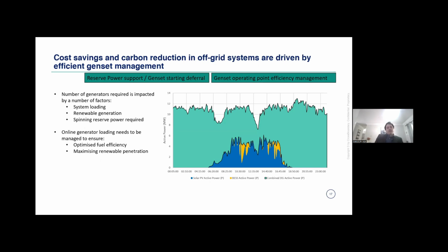Another critical application that we applied was on the reserve power support and genset operating point efficiency management. So when we look at a microgrid, obviously the number of generators that's required is impacted by the system loading, the renewable generation at the specific time, as well as the spinning reserve power required, which is a very critical aspect and which also reduces efficiency because you end up running more gensets than required for the possibility of losing a generator or sitting with curtailed renewable operation or possibility of an increased load for whichever reason.